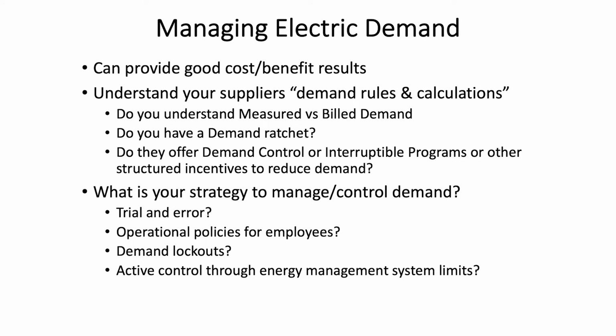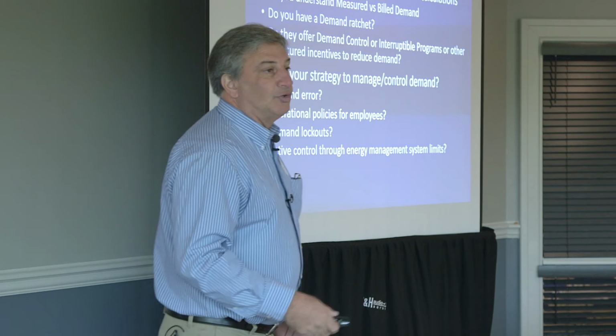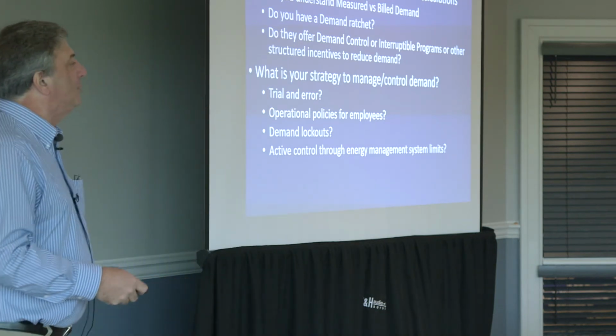Is it trial and error, where we just let employees turn on whatever they want whenever they want? Do we have operational policies for employees where we communicate that if X is on, Y should never run simultaneously? Do we have demand lockouts, where we put a piece of equipment in so that if X is on, Y cannot run? Or is it tied to our energy management system, where when demand reaches a certain level, the system automatically shuts off non-essential equipment? Those are all strategies people use to save a heck of a bunch of money.